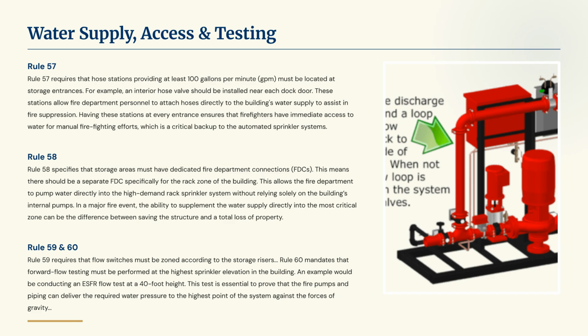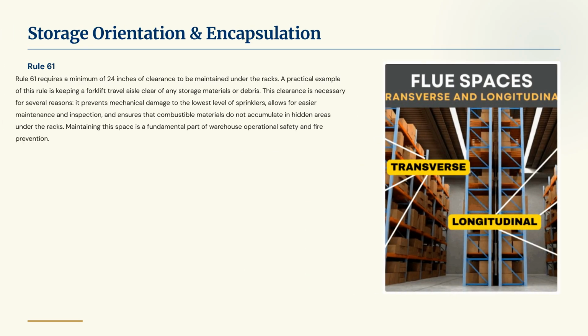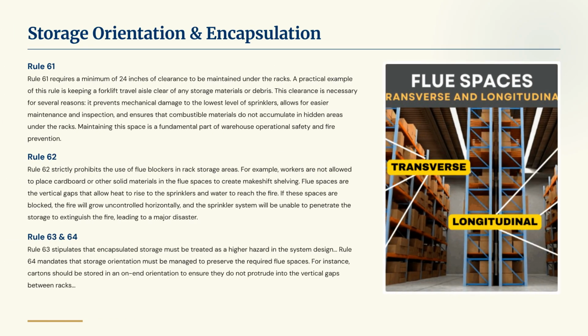Rule 58 specifies dedicated fire department connections for storage areas. Rules 59 and 60 cover flow switch zoning and forward flow testing at the highest elevation. Rule 61 requires a minimum 24-inch clearance under racks. Rule 62 prohibits the use of flue blockers in rack storage areas.